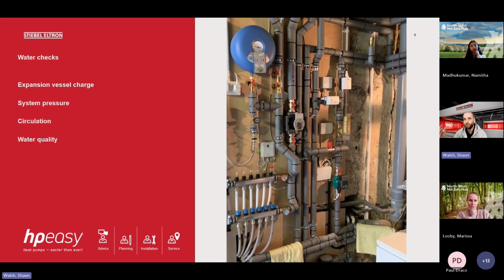Similar to a gas boiler, you still have system pressure, usually around 1.5 bar, for example. It operates in the same way. You have a little pressure gauge here, and you would make sure that it's up to pressure. Circulation. The heat pump manual will tell you what the flow rate of the system is, and depending on the size of the heat pump, they all require different flow rates to make them perform well. We can check that in the controller. We can check our flow rates and make sure that they're within the intended values. As I say, depending on the size of the heat pump, they can vary, so you need to check those as well.